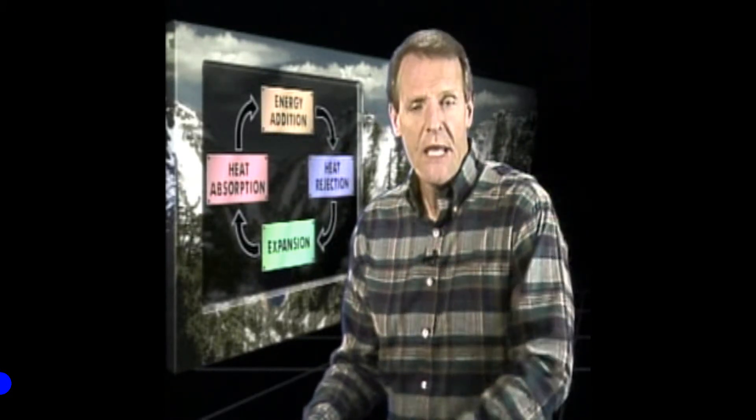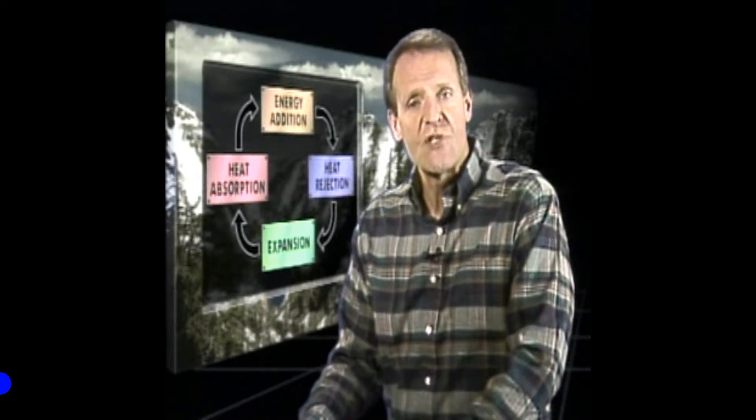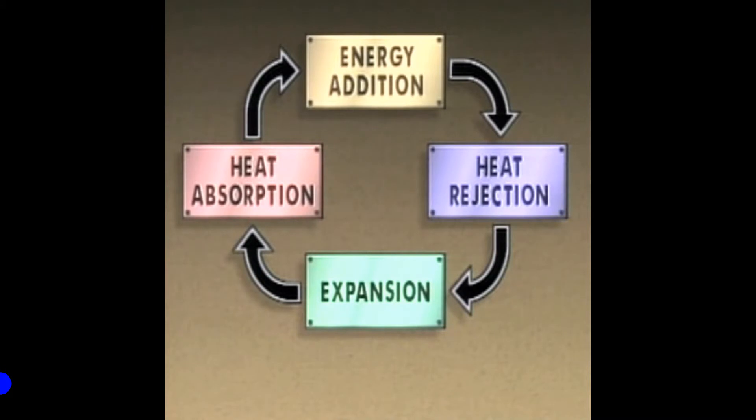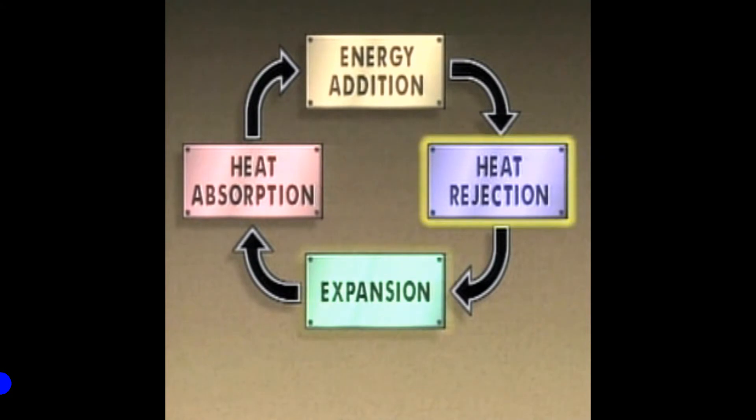The primary purpose of a refrigeration system is to remove heat from a substance. In most cases, removing heat lowers or maintains the temperature of the substance. To lower or maintain the temperature, a refrigeration system must be able to continuously absorb heat and then reject the heat from the system. This is done through several steps in what is called a refrigeration cycle. A typical vapor compression refrigeration cycle has four basic steps: heat absorption, energy addition, heat rejection, and expansion.